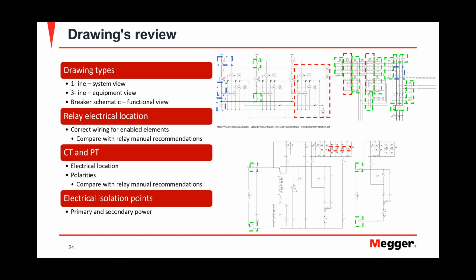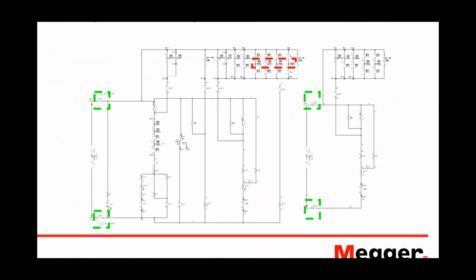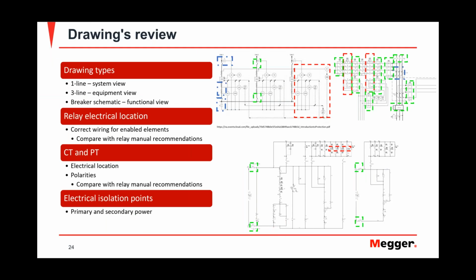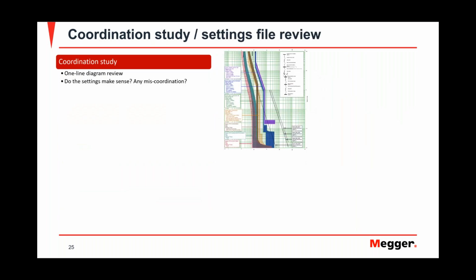On my three line, knowing where my test switches are, or the shorting blocks, or the main breaker, where those electrical isolations of primary and secondary power are, those are good things. On your schematic it is usually DC control. Usually you have a knife switch, or some plug-in fuses that you could take out to isolate the power. Being aware of that is something you should do to prepare for the job, so you know if you're electrically isolated even before you go there.